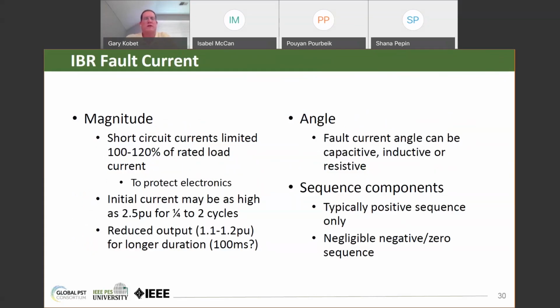The issue with IBR fault current. Now, the way that protection systems conventionally detect whether there is a tolerable condition or load carrying and an intolerable or a fault condition is by a few different, what Blackburn in his protective relaying textbook calls handles. When a fault occurs, typically in a conventional power system, the voltage sags, decreases, the current magnitude increases, and the current phase angle becomes more lagging relative to the faulted phase voltage.